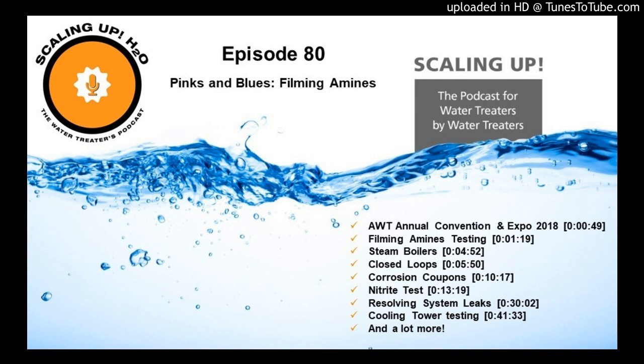So how much of a residual do you have? Well, here's how I gauge that. Most of the tests are pink, but if yours isn't, let's just substitute the word pink for whatever that color is. If it is a little bit pink, it means you have a little bit of residual. If you have a lot of pink, you have a lot of residual. Now, how much of either of those, I don't know, but the whole point is you just need to make sure you have a residual, and that means that if the coating somewhere in your system gets rubbed off, you have plenty to replace it.